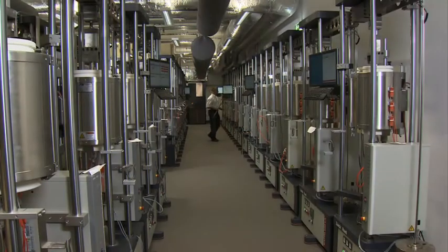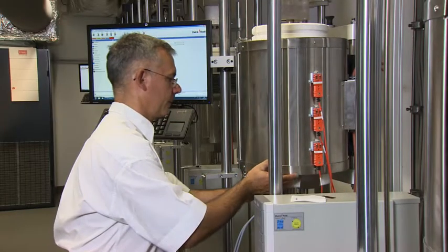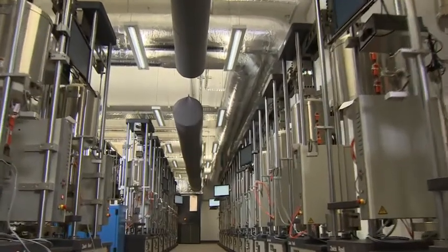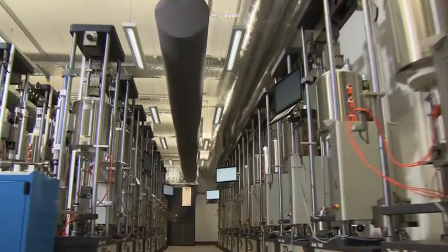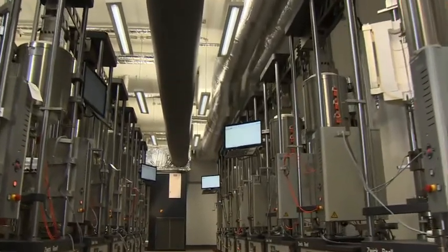It is particularly important that steels used in power plants operated at elevated temperatures be resistant to creep rupture. We carried out 164 tests to verify the creep behavior of VM-12 SHC. In furnaces, specimens under tension were exposed to temperatures of 525 to 700 degrees Celsius for over 1.3 million hours in total — corresponding to about 150 years. The results obtained for VM-12 SHC are comparable to those of P-91 steel.